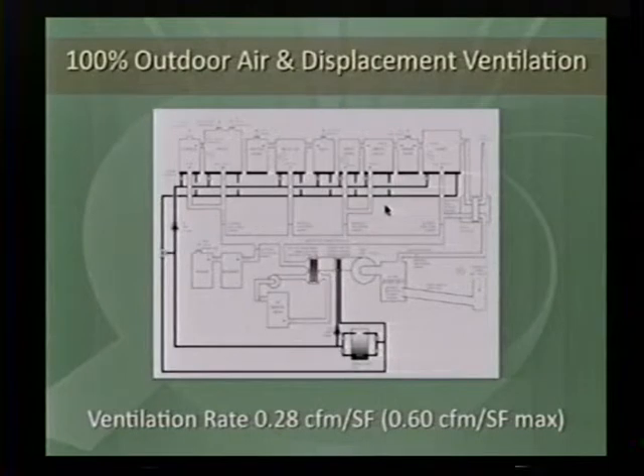100% outdoor air and displacement ventilation. Basically, this diagram is probably a little bit more detailed, to get a whole bunch of information out of it. Mainly, we basically have the radiant floor slab and the air coming in low from the air handling unit, which is a VFD drive fan. Then all of these spaces, diagrammatically all of the occupied spaces, have direct exhaust to the outside. Okay, so we're basically carrying the air through and exhausting it. We do have the exhibit space set up, so if there's a large group and we have to add more air, that additional air comes with an enthalpy wheel that adds another 750 CFM, and we're doing some energy recovery.